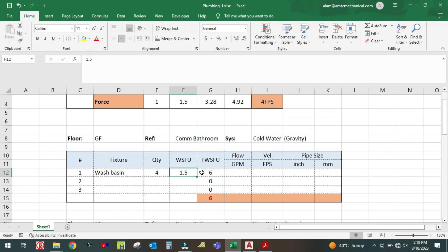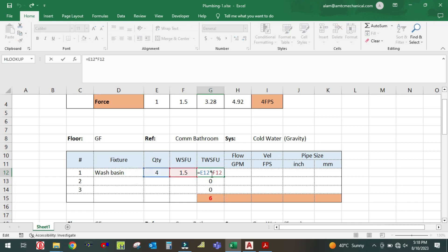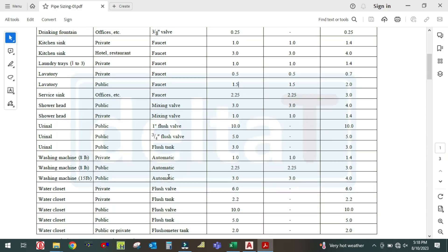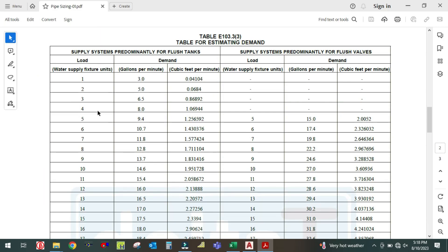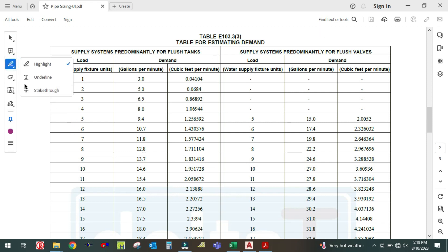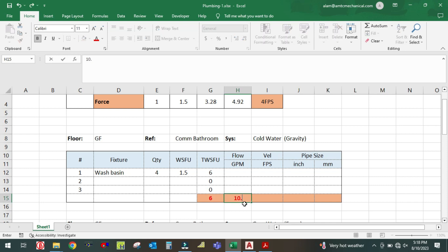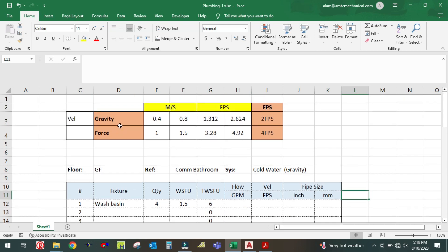1.5 multiplied by 4 gives a total fixture unit of 6. For 6 fixture units, the GPM is 10.7 GPM. The velocity is 2 feet per second for a gravity system.